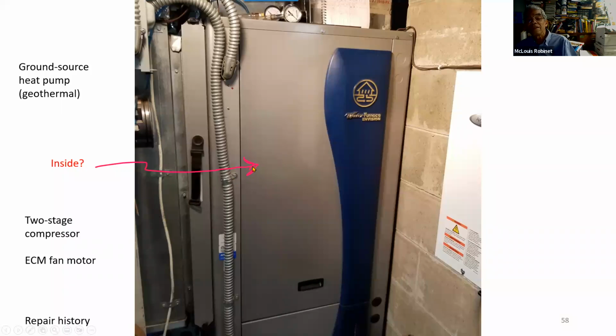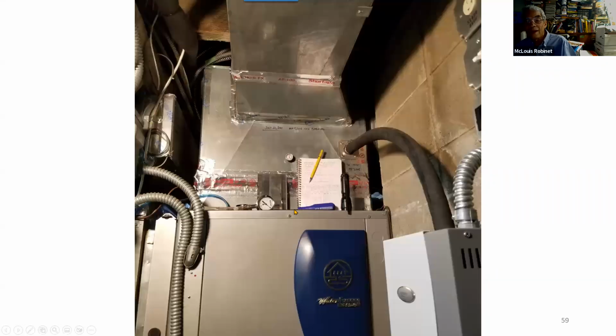A couple months later, I came in and found water on the floor. It turned out there's a drip pan here. The drip pan had a crack in it, but I was able to fix it with some aquarium cement. About a year ago, the other failure was that the system wouldn't start, and it was a $20 starting capacitor. So it's not bad for 11 years. The loop field is outside. This guy said he would keep an eye on it.